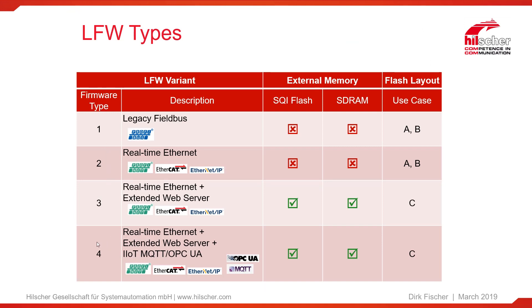On the next slide I show you a table which summarizes the different firmware types. As you can see, Type 4 — the full-blown version with OPC UA, MQTT, and the extended web server — requires external flash and external SDRAM, so we need more hardware components. The flash layout is called use case C, which is explained in other video tutorials. In contrast, Firmware Type 2, without the extended web server and without IoT protocols, does not need external memory. So it's possible to have a smaller, cheaper hardware.